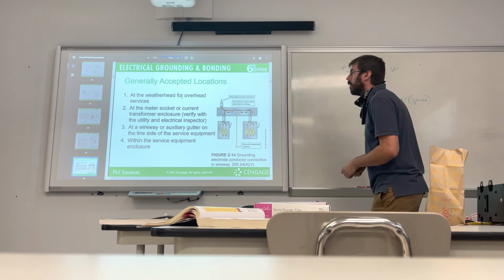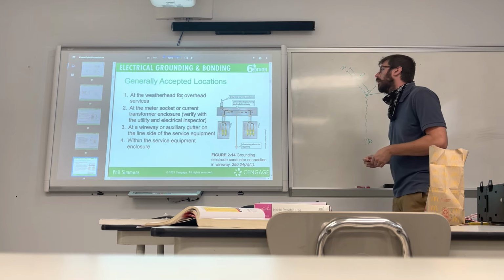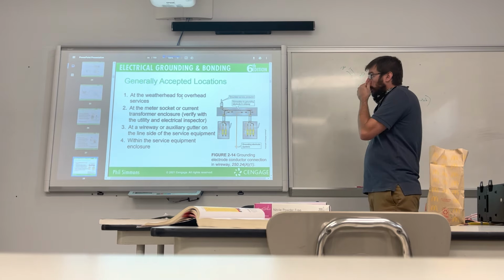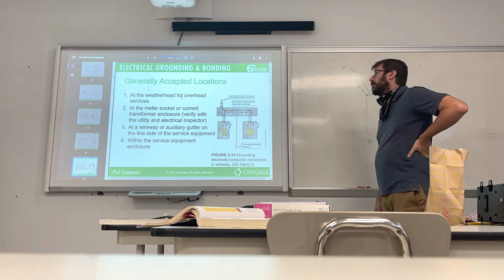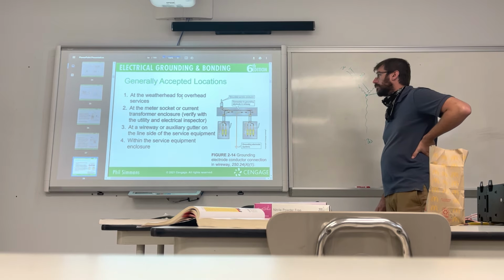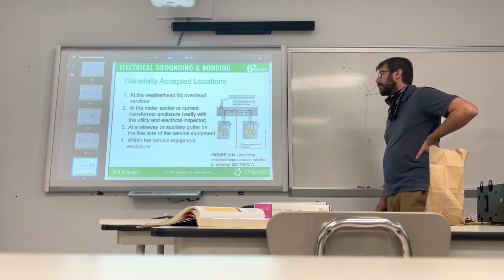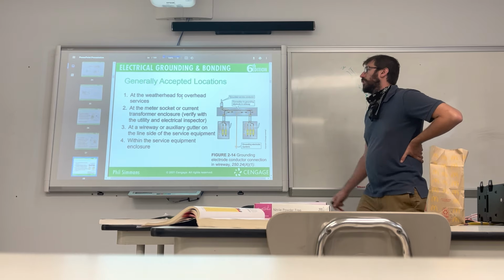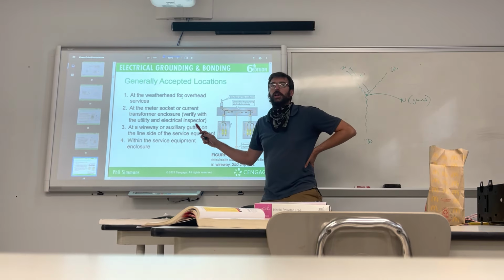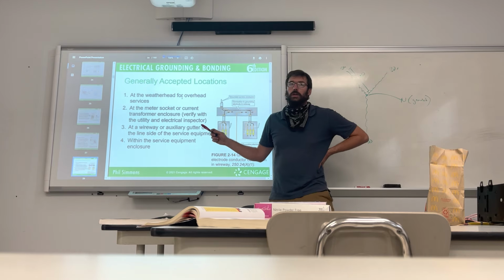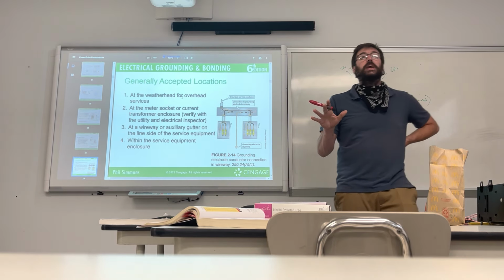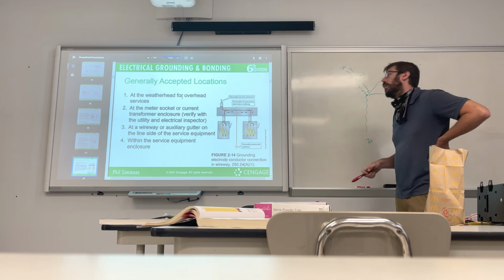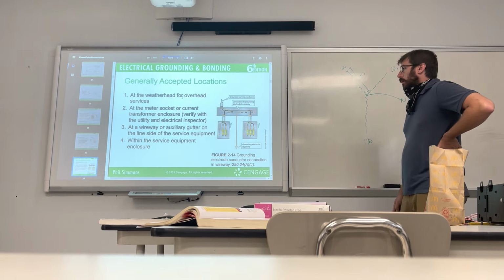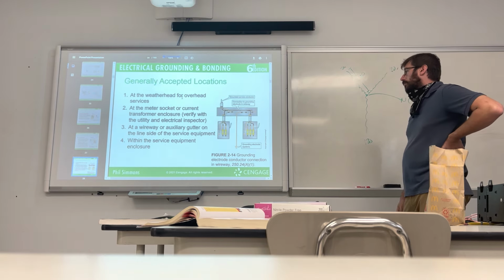Generally accepted locations are at the weatherhead for the overhead services, at the meter socket or current transformer enclosure, verified with the utility and electrical inspector. Once again, that electrical inspector in this area, I guarantee you ain't gonna like the meter base. You ain't gonna like that, not one bit. There's only a couple instances where you have to, and they're few and far between. Continue. At a wireway or auxiliary gutter on the line side of the service equipment within the service equipment enclosure.